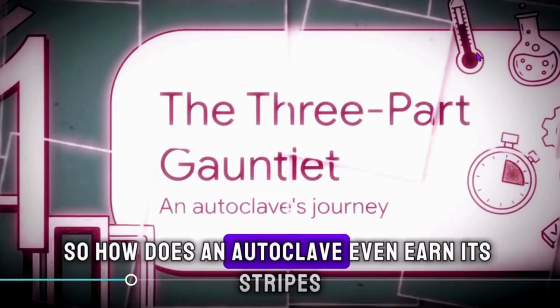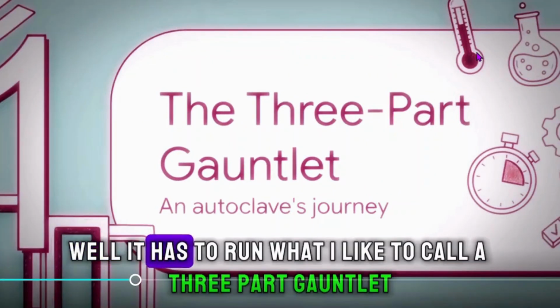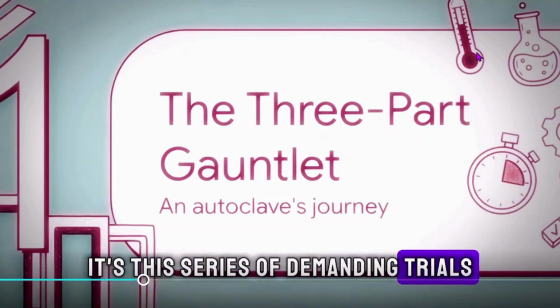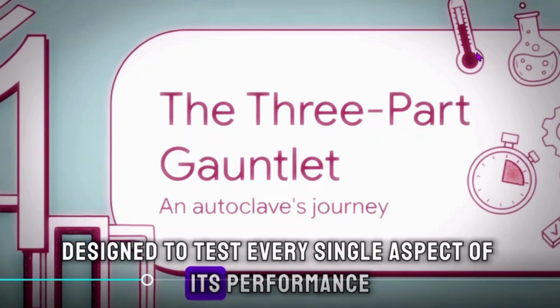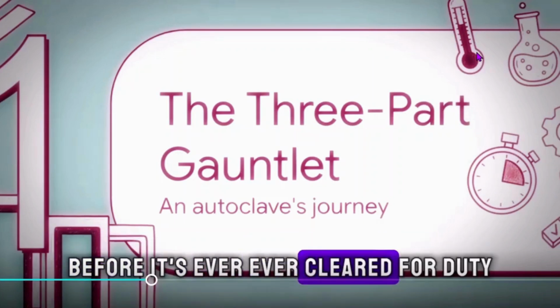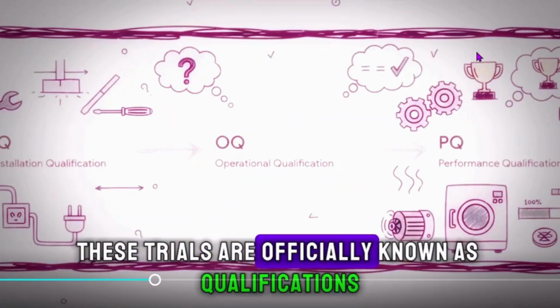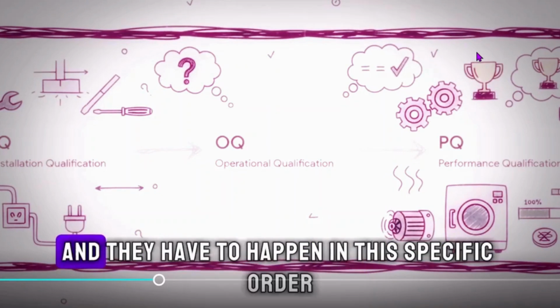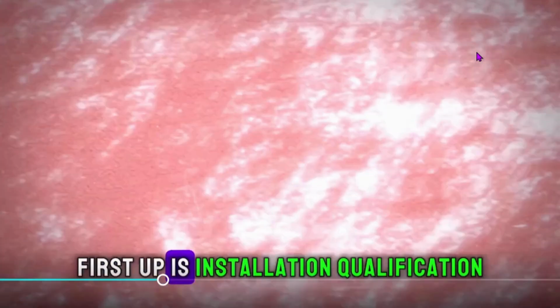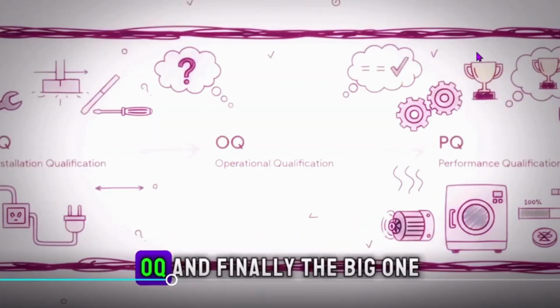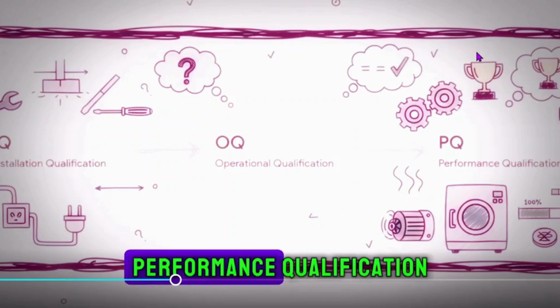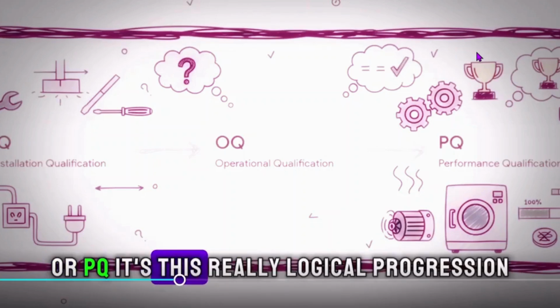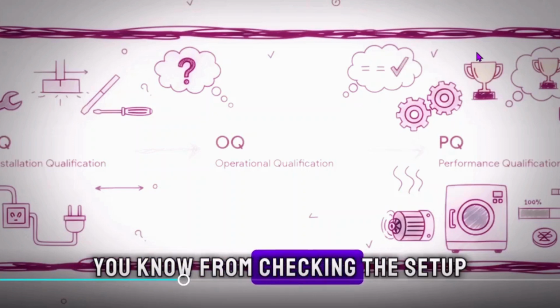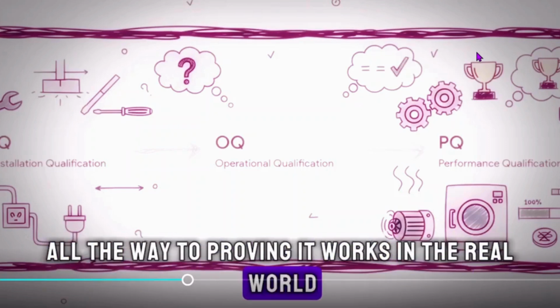Okay, so how does an autoclave even earn its stripes? Well, it has to run what I like to call a three-part gauntlet. It's this series of demanding trials designed to test every single aspect of its performance before it's ever cleared for duty. These trials are officially known as qualifications, and they have to happen in this specific order. First up is installation qualification, or IQ. Then you have operational qualification, OQ, and finally, the big one, performance qualification, or PQ. It's this really logical progression, from checking the setup all the way to proving it works in the real world.